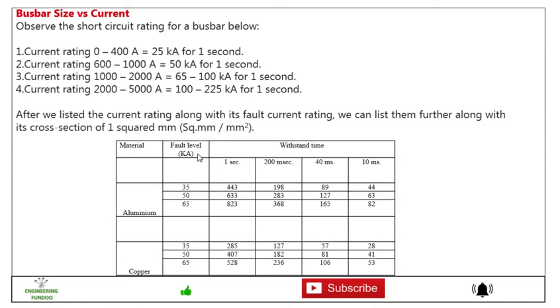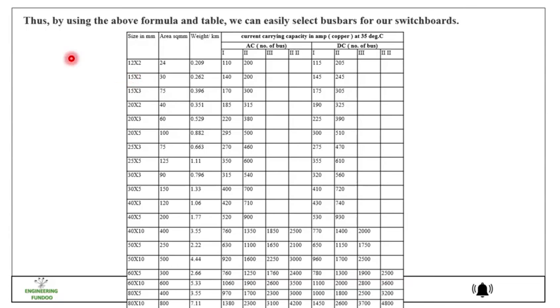And for 35 kA withstand time for 1 second it will be 443 square mm. For 200 msec it will be 198 square mm. You can see for different withstand time there are different ranges of cross section available from this table. So this cross section you can select depending on fault level current and withstand time. So this is also one of the method by which you can select the busbar cross section.